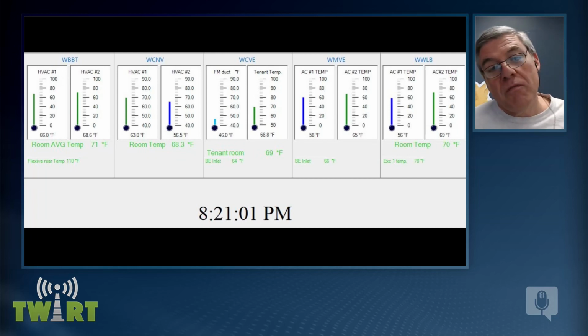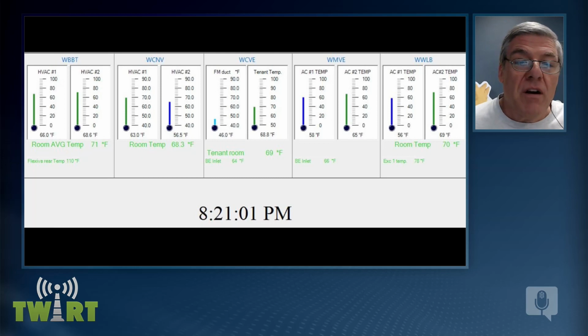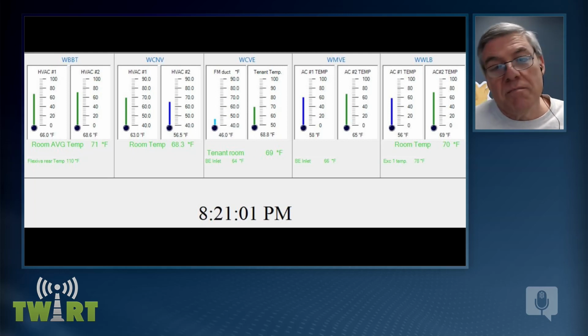Because Burk provides color code capability when you're doing any of their customizations, blue is saying the unit is running in some form or another. Like the one on the right, HVAC number 2 at the site, shows 56 degrees and it's blue. I'm not sure exactly what I've got the threshold set to, but somewhere between 56 and 63. And if you look down below, it says the room temperature is 68.